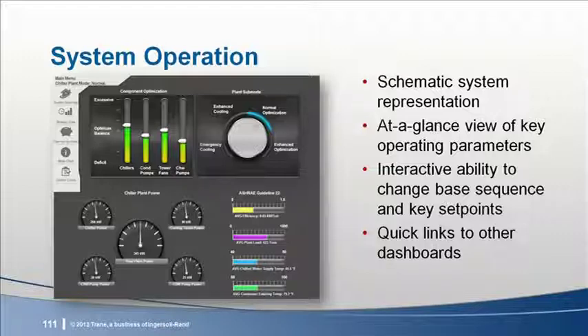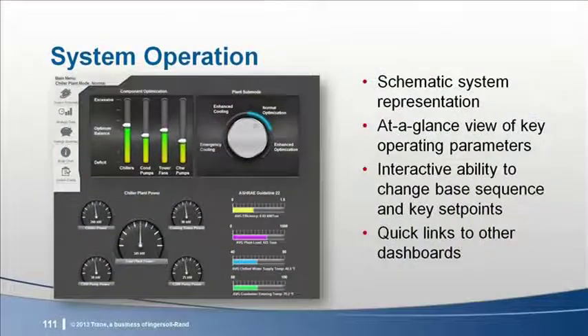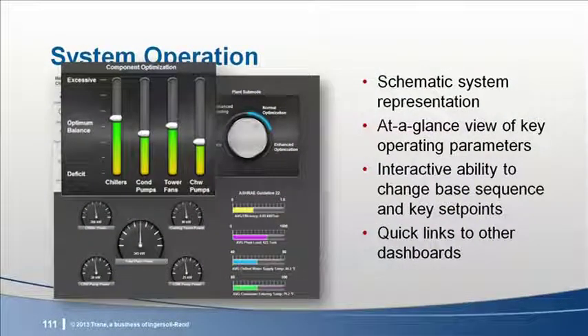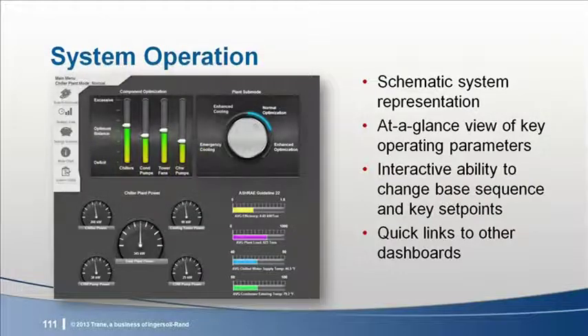Metrics such as system temperatures, pressure, cooling load, as well as system kW per ton versus ideal and system reset values would be valuable. One of the challenges operators face is understanding if the optimization strategies are functioning properly. And if not, what is not working as it should be? Since we've discussed the importance of proper energy intensity balance between components, a plot of the current state of component operation would not only assure the operator of acceptable operation, but could identify and further diagnose any operating imbalance.